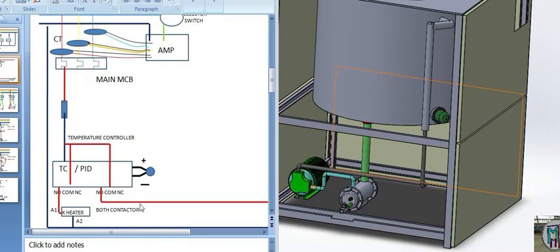And in the PID we can set the value of the difference between the two values, for heating and cooling also. Suppose we need a temperature of 40 degrees, we can set our temperature to 40 degrees, but inside we can set for the cooling system 40 degrees with a plus or minus of 1 to 1.5 degrees to operate both systems. It is not possible that heating and cooling will be on at one time. So we recommend every time that you fix a PID besides your temperature controller. Now, what is the working of this?